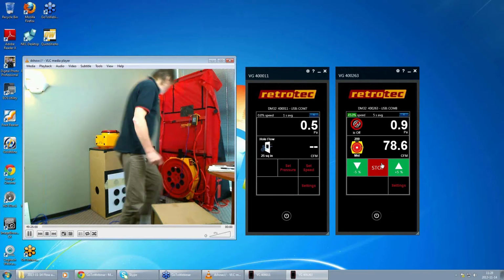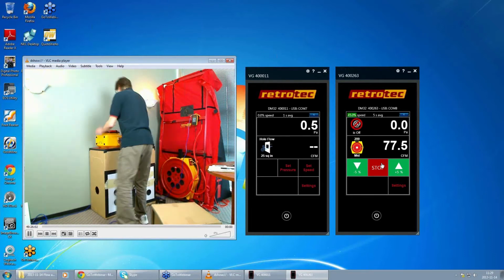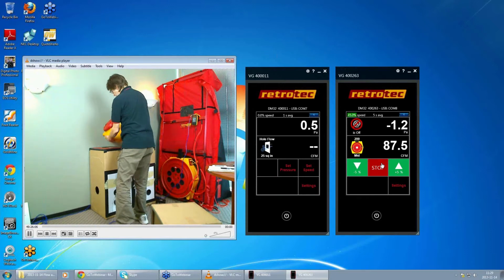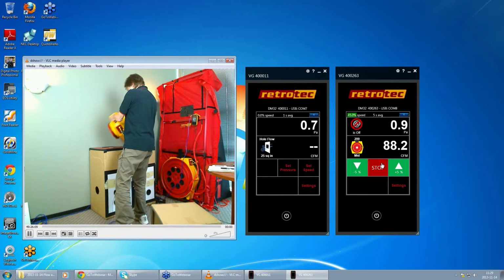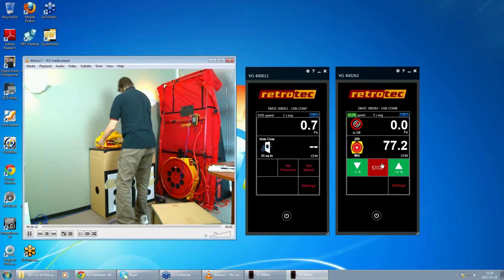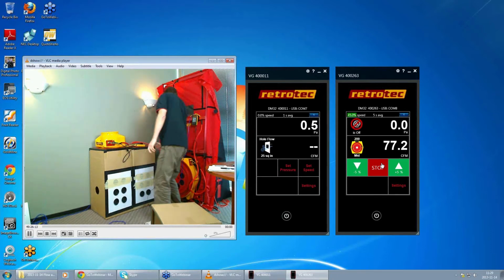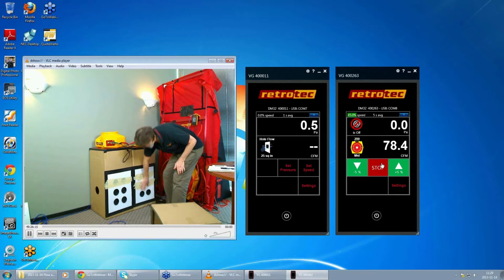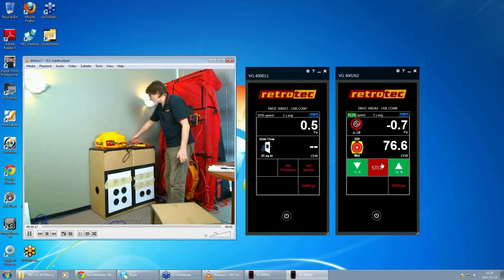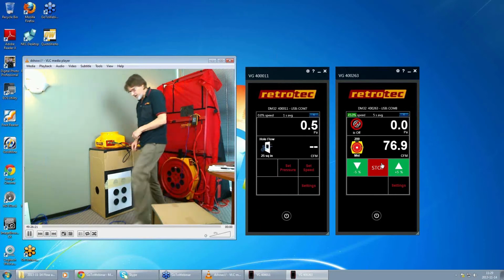So we're going to go back to the negative mode that we had before, sucking air out of the box. For your information, we've got a bunch of holes in here. All these holes are sealed off. These are sealed off. There's another hole in the top. It's sealed off. There might be a tiny bit of leakage in there, maybe a CFM here or there.